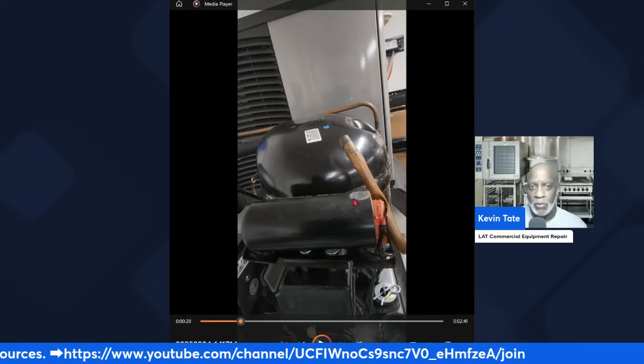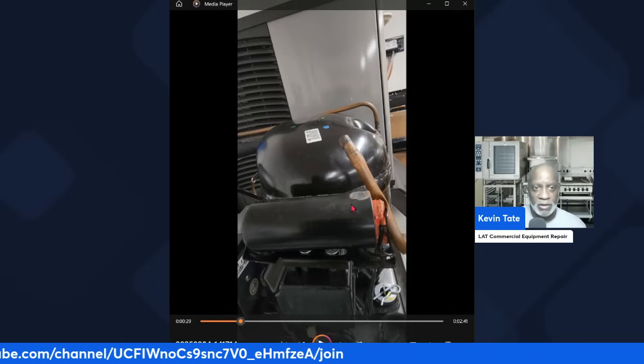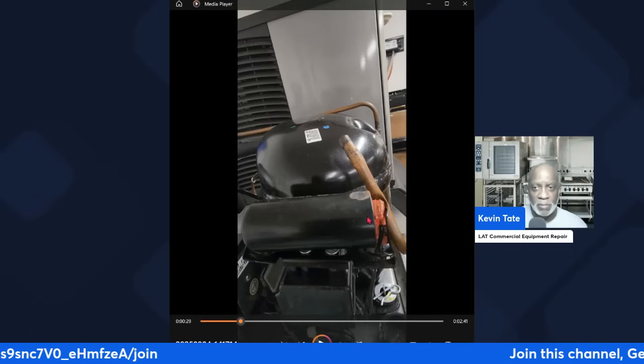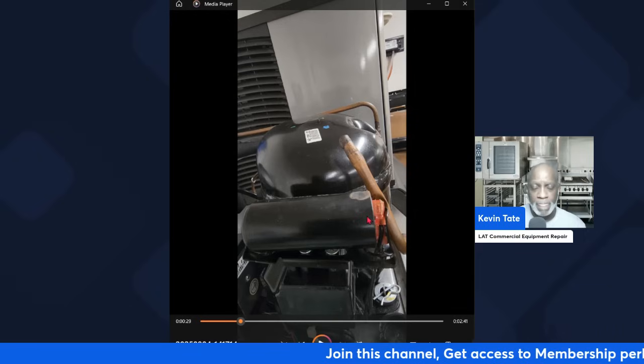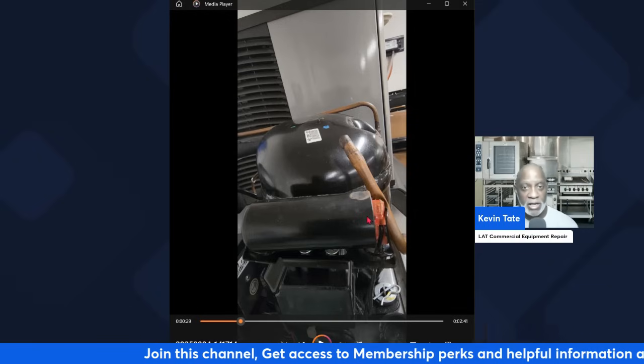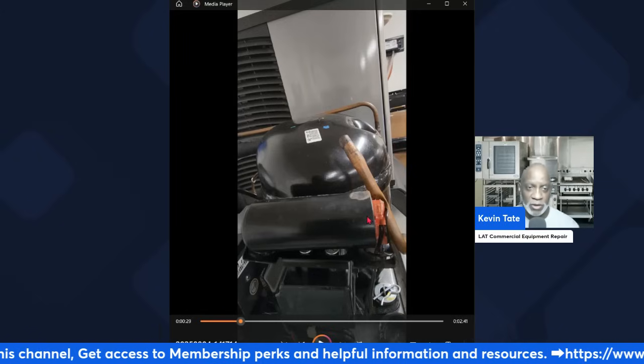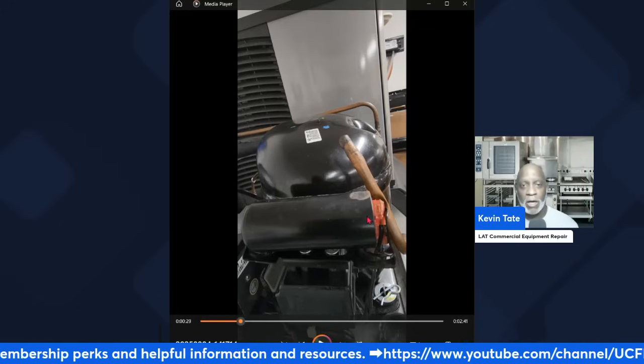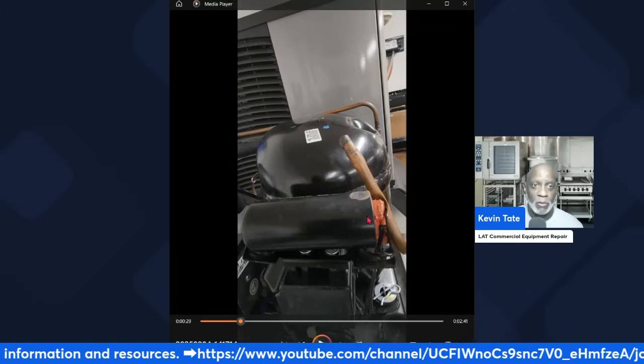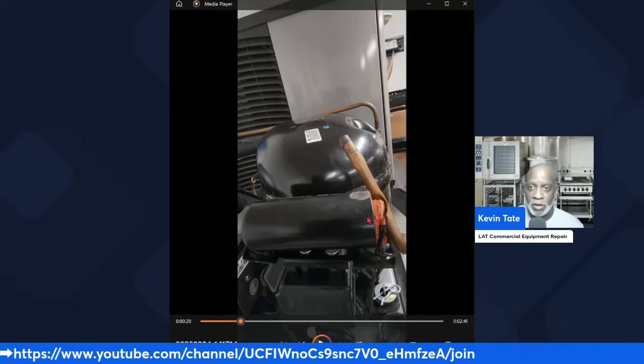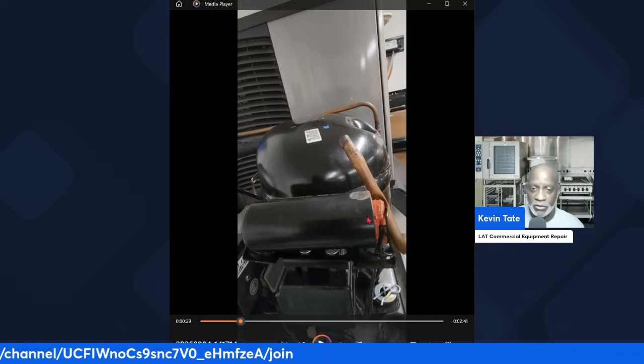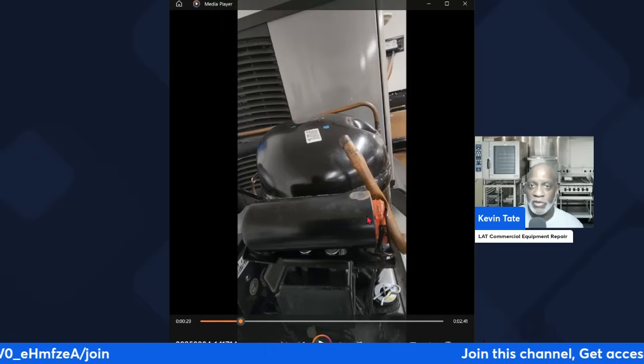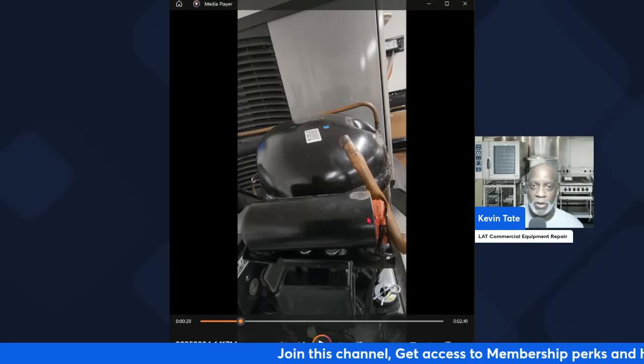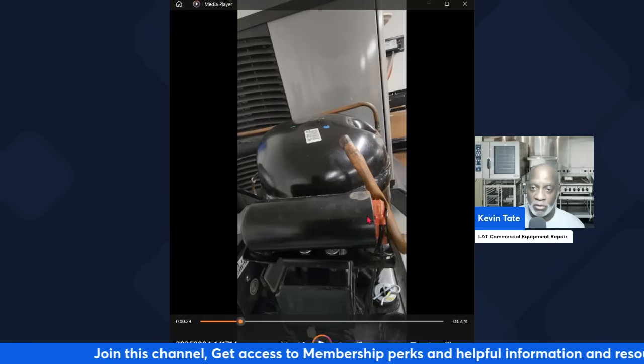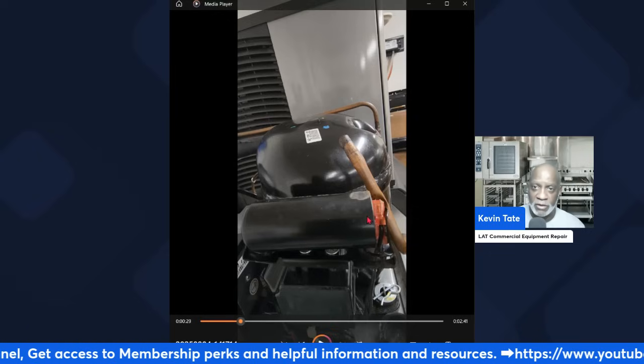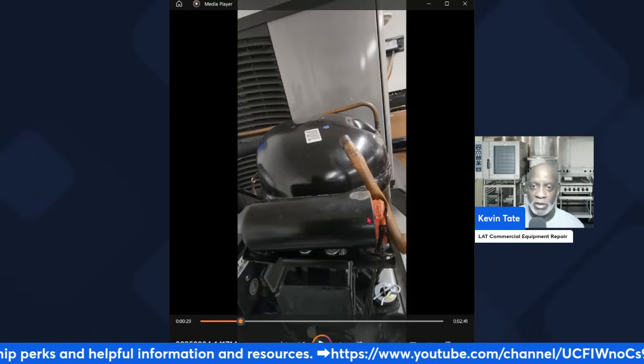So I went ahead, shut down the unit, unplugged it, disconnected the capacitor, removed it from the bracket, and then discharged it. You really should discharge the capacitors before you take any measurements or work on it at all. Just as a safety note, be sure that you discharge your capacitor. If you're not familiar with discharging a capacitor, you can go into the playlists on this channel - there are some videos there for properly discharging a capacitor.